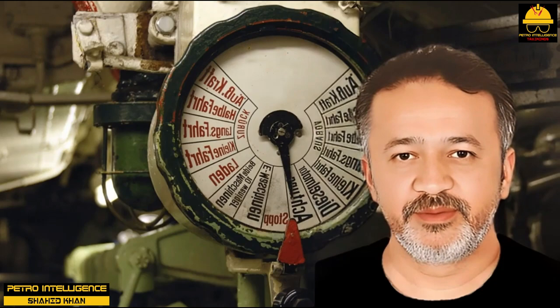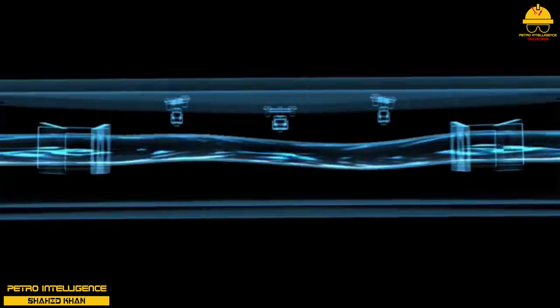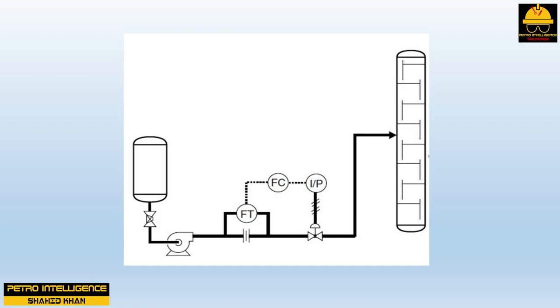The Coriolis meter is a true mass flow meter that uses a vibrating tube to measure changes in momentum or mass flow rate; it is very effective for precise measurements of mass flow rate. Flow control loops are typically designed so a measurement of the flow rate is taken first, and then the flow is controlled downstream. Flow control loops start at the primary element, which could be an orifice plate, venturi tube, flow nozzle, nutating disc, oval gear, or turbine meter; the most common is the orifice plate.